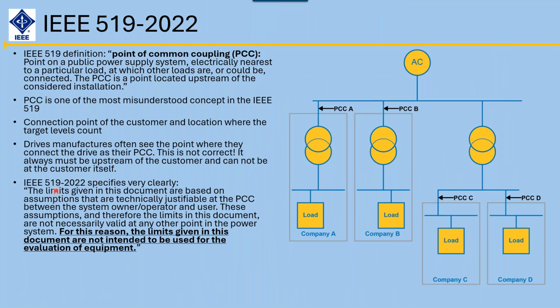So IEEE 519 clearly specifies the limits given are based on the assumption that all technical justification is at the PCC between the system owner, operator, and user. These assumptions, and therefore the limits in this document, are not necessarily valid at any other point in the power system. For this reason, the limits given in this document are not intended to be used for the evaluation of equipment.